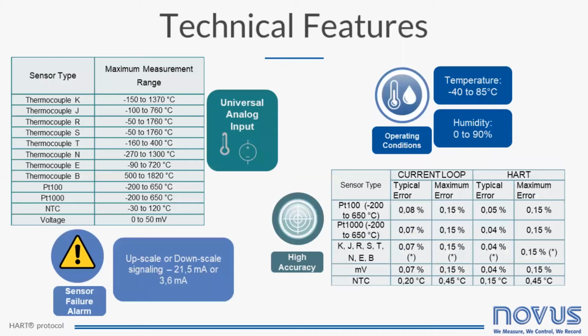As you can see on the accuracy table, it has two different values for each type of sensor. When the temperature value is read digitally by HART, the error of the current loop could be discounted. In other words, it has more accuracy in the measurement process.